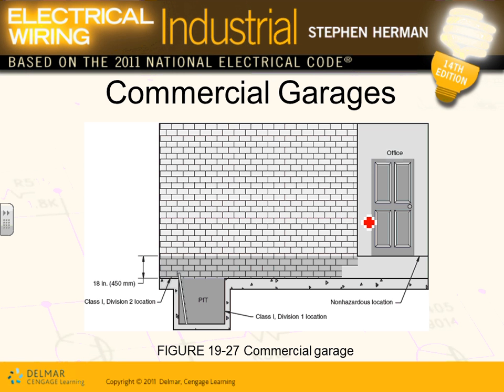Okay, here's the commercial garage. They're fixing your car right here, and they don't use pits because of safety anymore. Remember when they used to drive your car over a pit? Some places still have them, and instead of lifting the car, they go underneath and fix it. If you have a pit like this in a garage, that pit is class 1, div 1. 18 inches above the ground, this area is called a class 1, div 2 location.